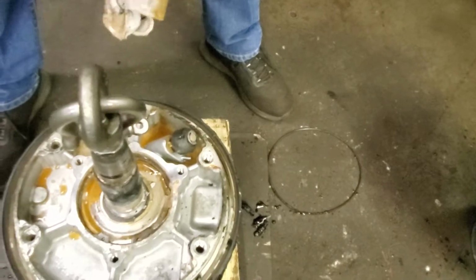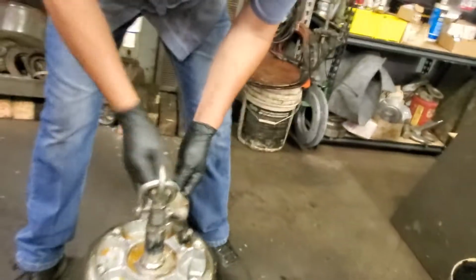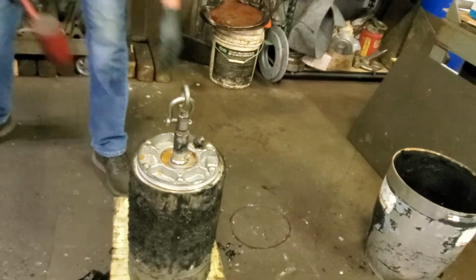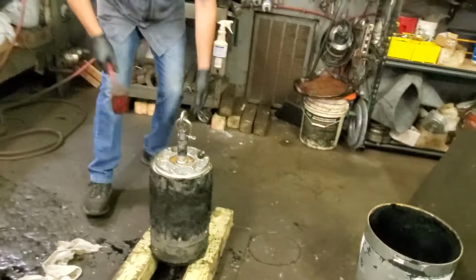There's the FLS switch, the FLS right here. Because it's stuck right here, that's what the FLS shows. I didn't think so before they pulled the water, but whenever we pulled the pump out of the hole, the seal had failed. So what happened? The water leaked out. Right. It leaked out because the seal failed. Yes, the seal failed.